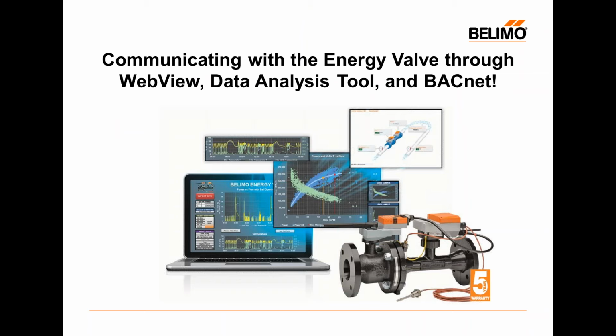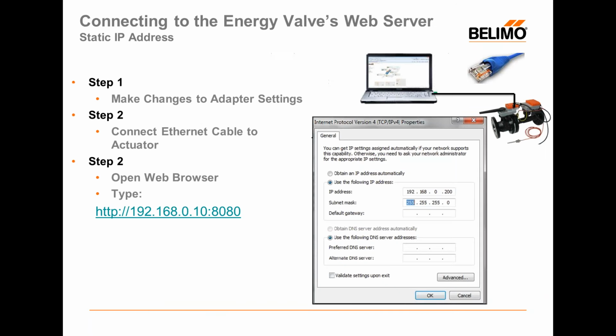Today we're not really going to talk about the functionality of the energy valve, but more the communication side of it, how we tie into it, how we make adjustments to it, and how it can be connected to via BACnet. For those of you who do or don't know, the energy valve has both an embedded web server as well as a BACnet application-specific controller in the valve's actuator itself.